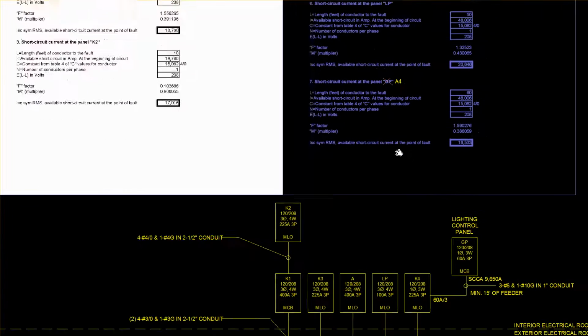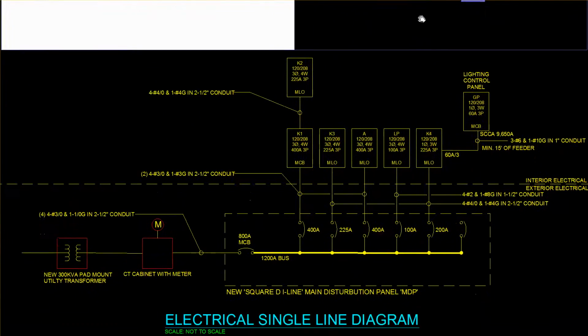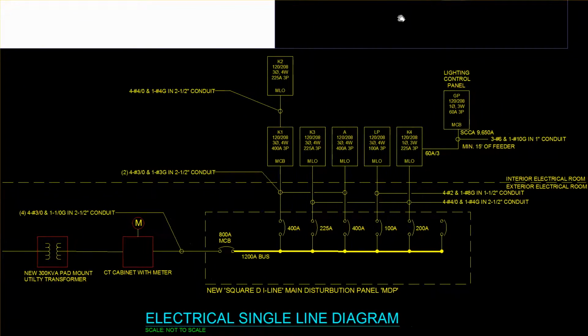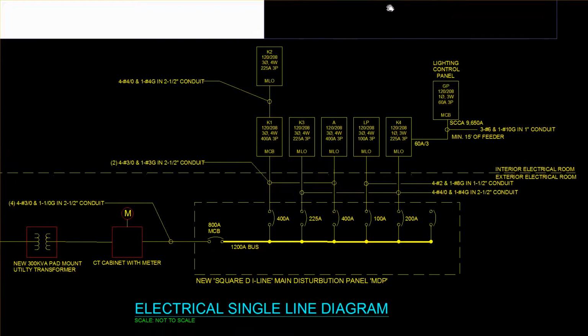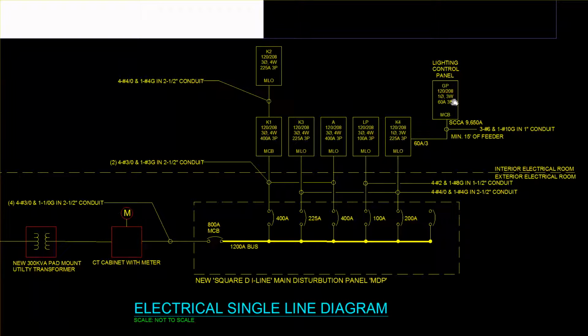And so those are worst case scenario. We call that a bolted three-phase fault, which is what would happen if, let's say, we were to go into our bus and this panel board, turn the power off, run a bolt through all three of the phases, and then flip the main back on. It would have theoretically an available 9,650 amps of current available to it. And so we have to protect for that. And so these are the basic components that we're looking for in a one-line diagram.